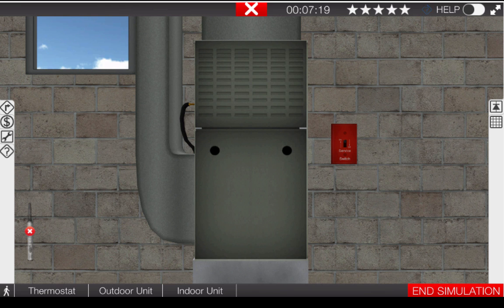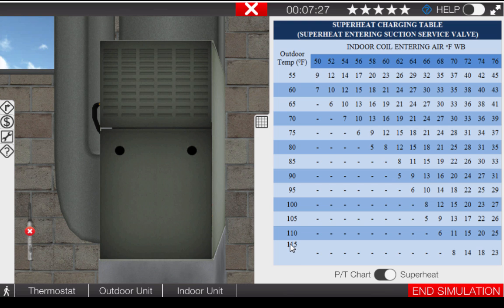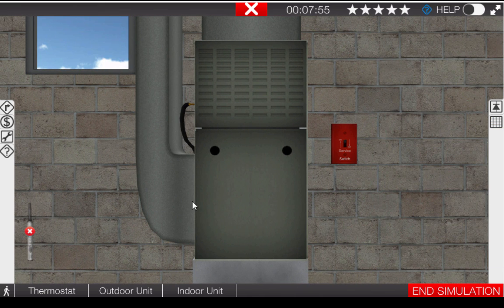Placing the thermometer back in the toolbox, we're going to click on the right tab again. At the bottom of the temperature pressure chart, click superheat. This provides us with the superheat charging chart, which will help us verify and correct the charge. Looking at 95 degree outdoor temperature and 70 degree wet bulb, we can see these intersect at 18 degrees of superheat. This means that if the unit is charged properly, we will have 18 degrees of measured superheat. Any measured superheat within plus or minus 5 degrees of the target of 18 is acceptable, meaning 13 to 23 degrees would be okay. We already know that we have 49 degrees of superheat, which is very excessive, indicating again that we have an undercharge or a leak in the system.